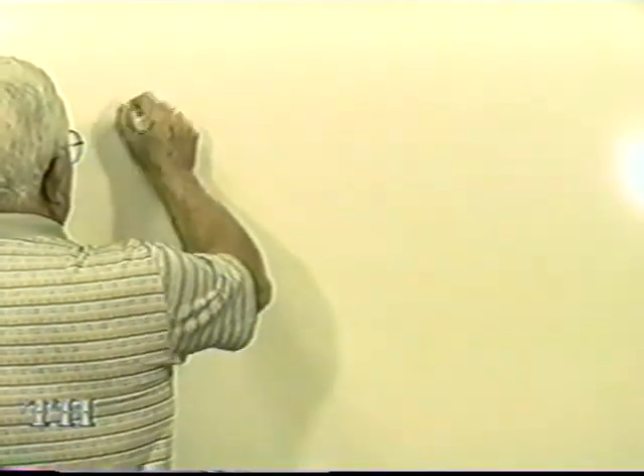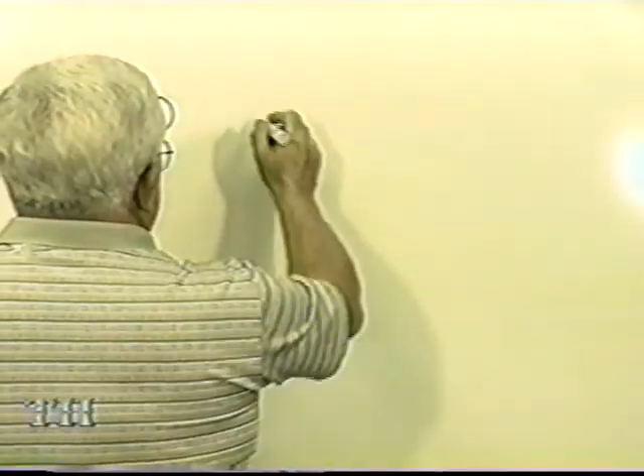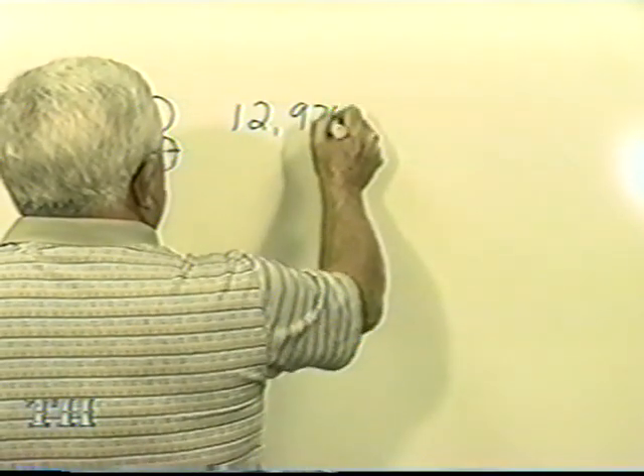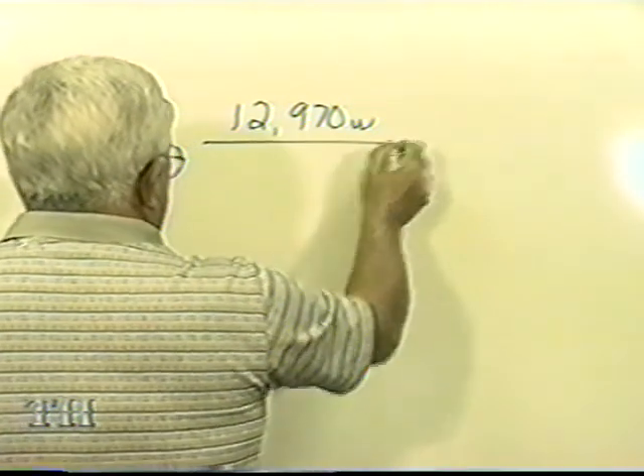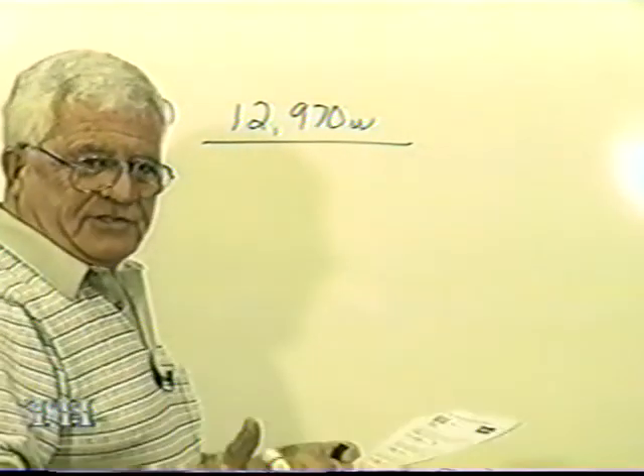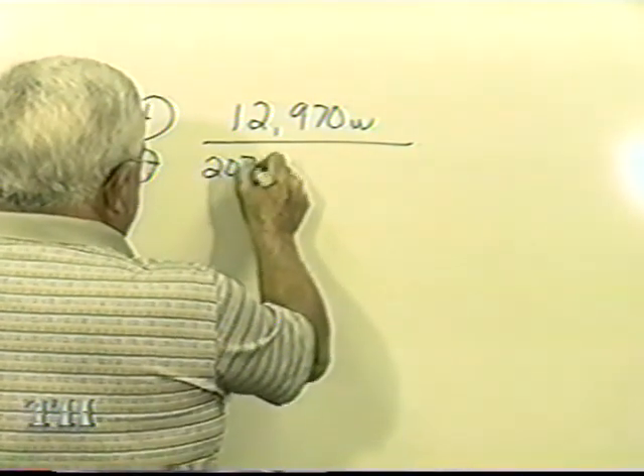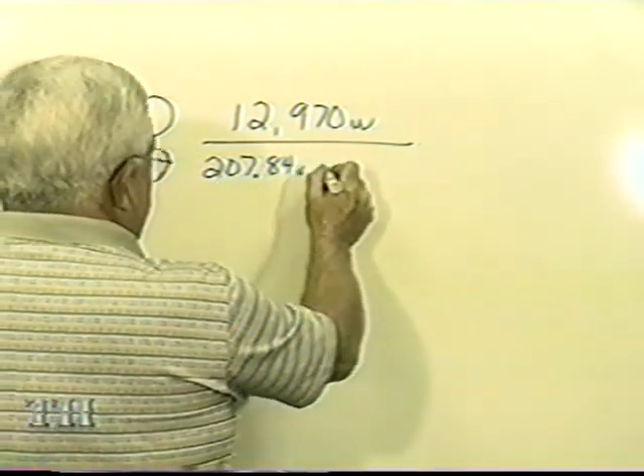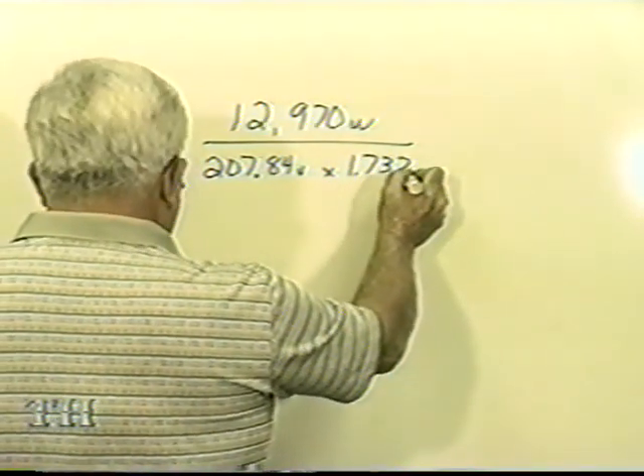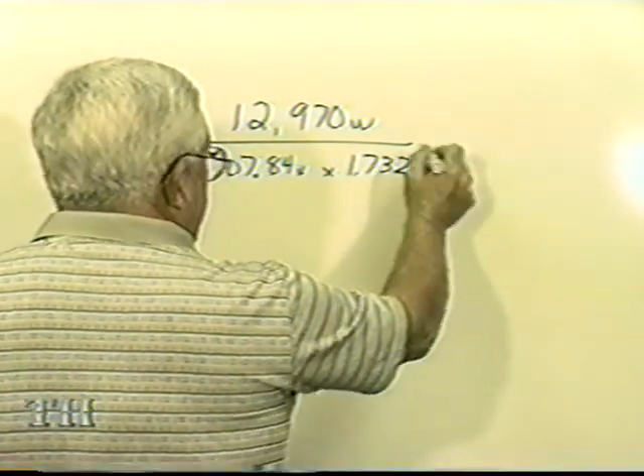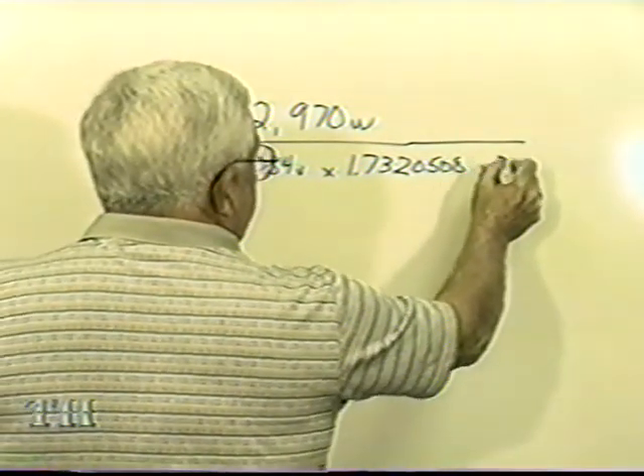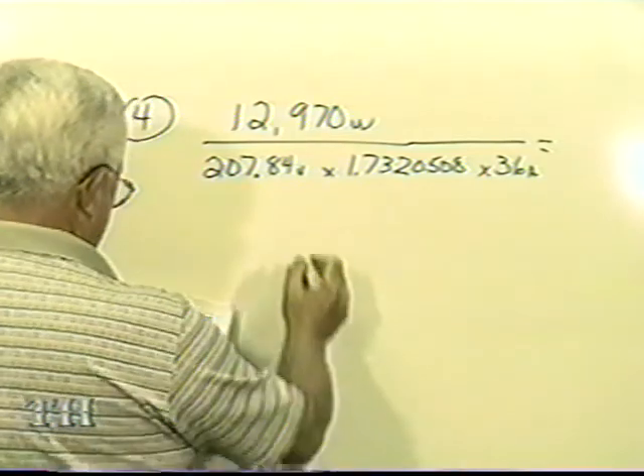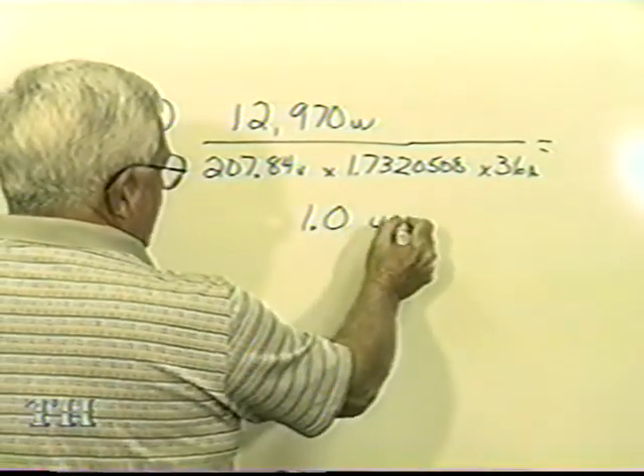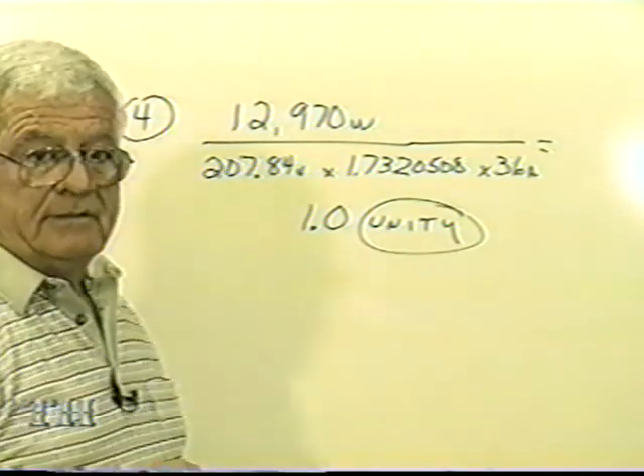Now number 4 talks about a watt meter reading. Same type question. If I would take 12,970 watts, instead of using 208 and the square root, I'm going to round it out so I can come closer. The voltage is 207.84 volts times the square root of 3, but I'll carry it all the way out in my calculator just to have some fun, times 36 amps equals. It's pretty close enough to call it unity, the correct answer.